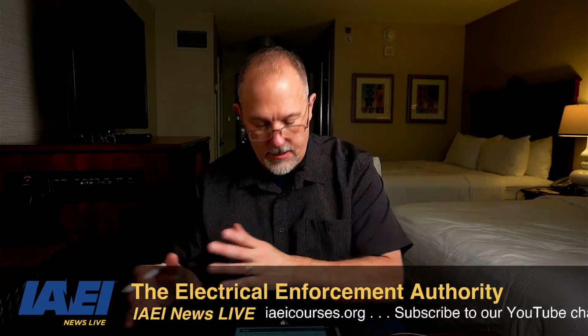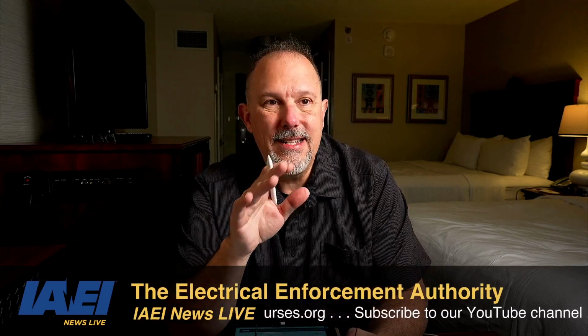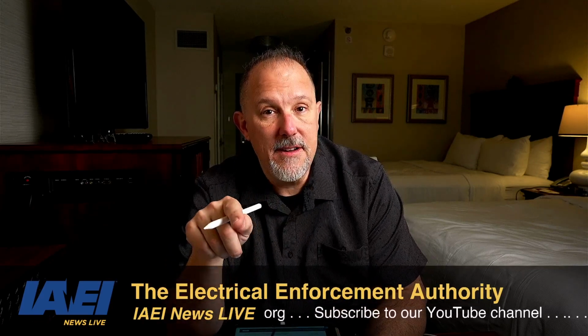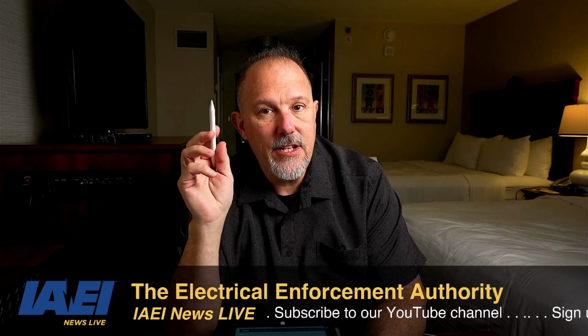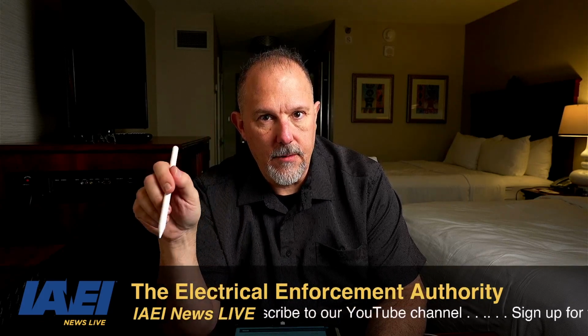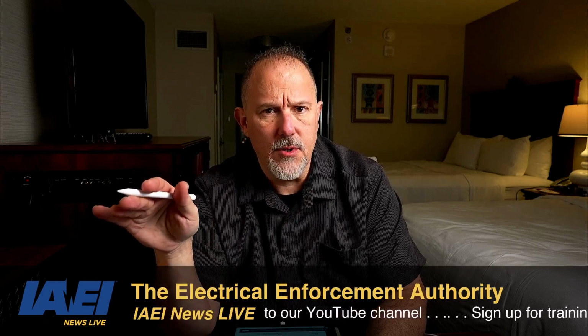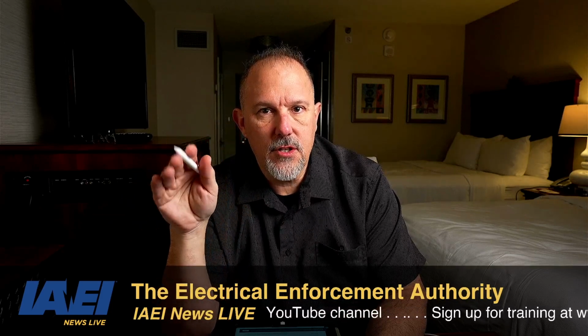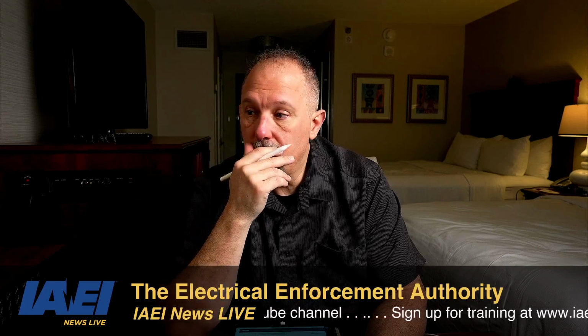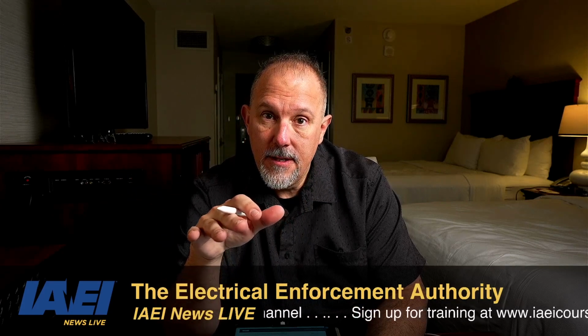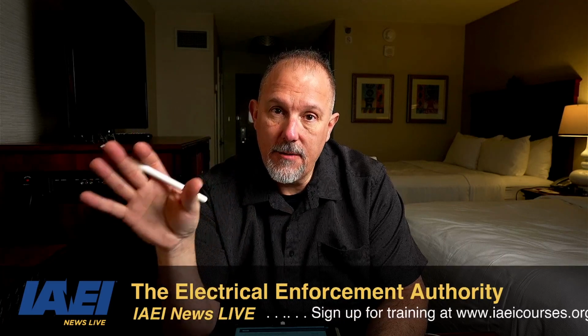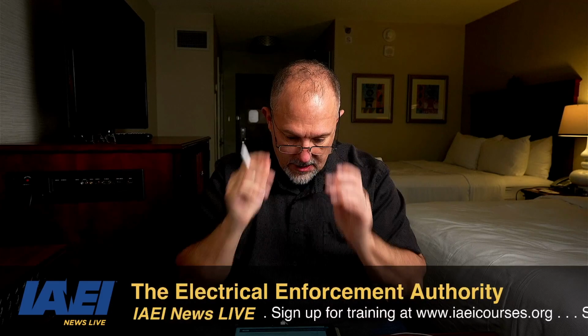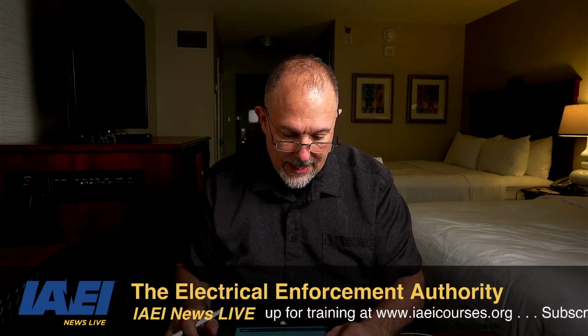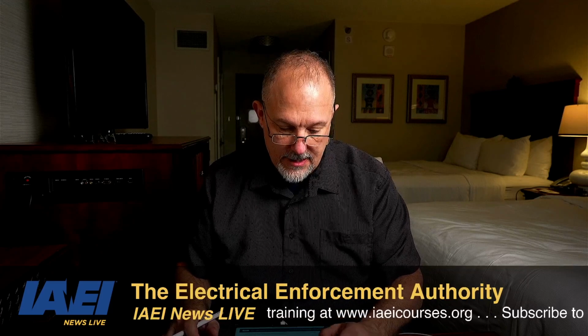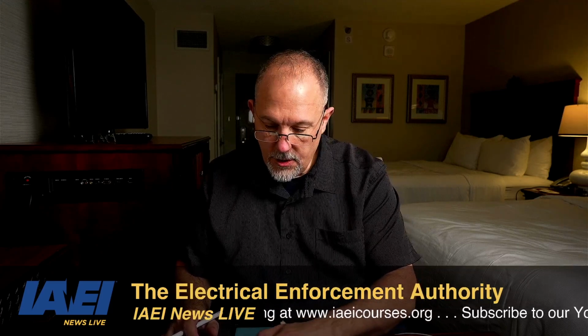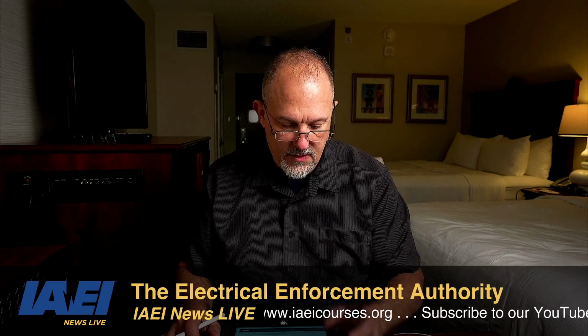That's not the generator. We know the generator typically comes with a breaker, but not all the time, right? So if I don't have a circuit breaker on the generator, and say I'm paralleling generators or whatnot, those are still feeders because the generator is a source. Now let's go look at the definition of a feeder. I know we talked about it last week as well, but I've learned about definitions: you can never read definitions enough.